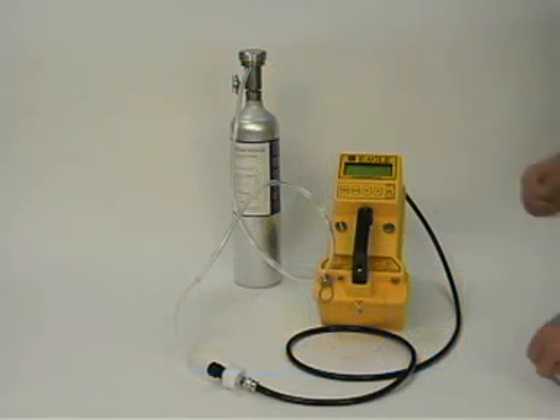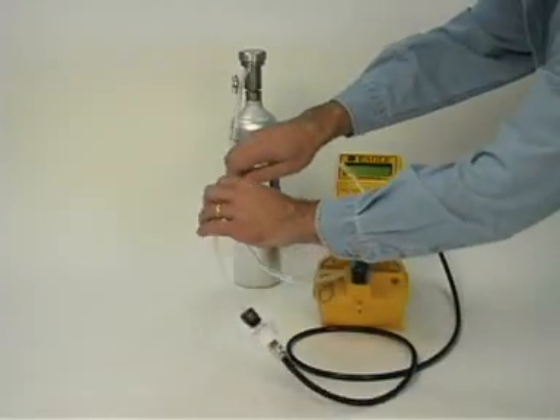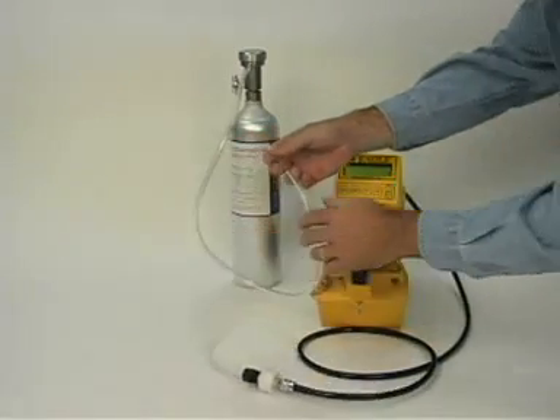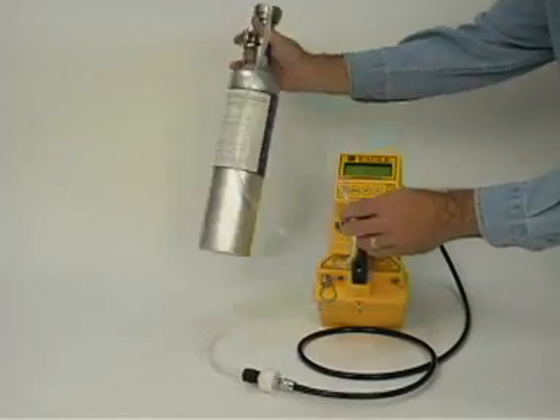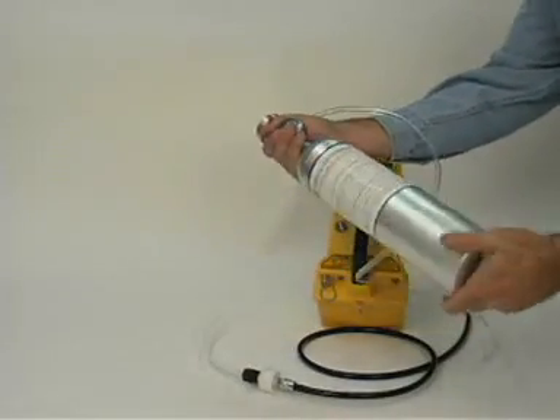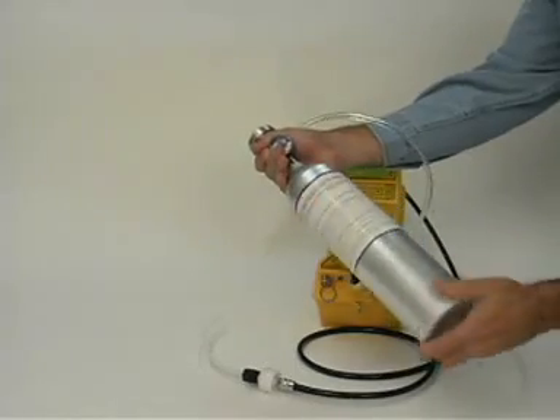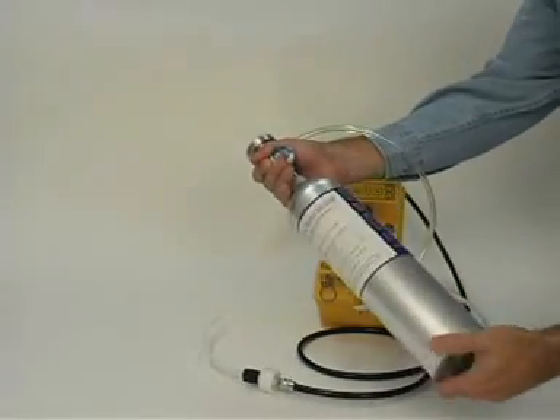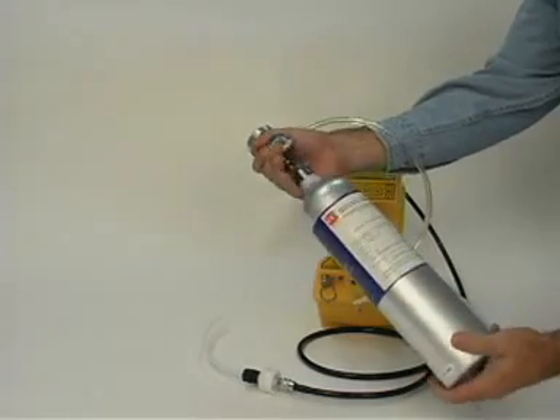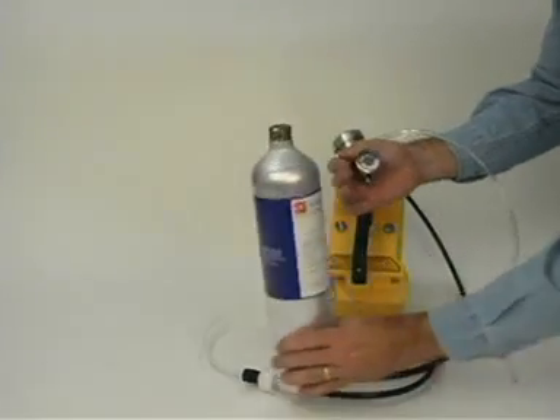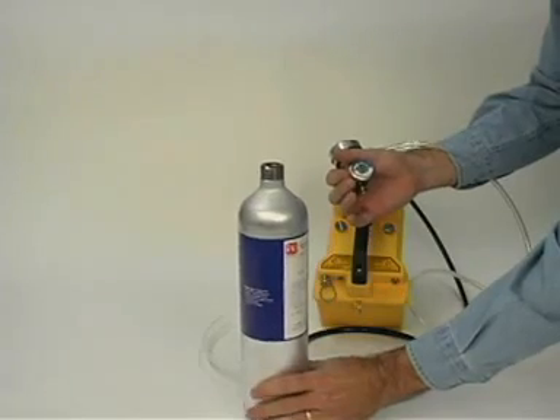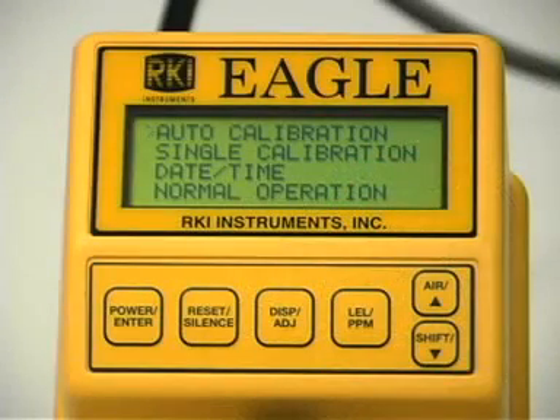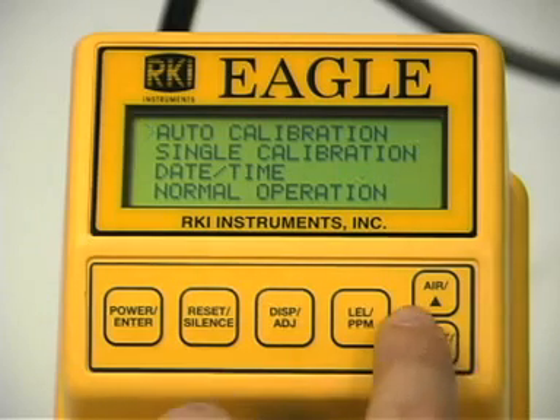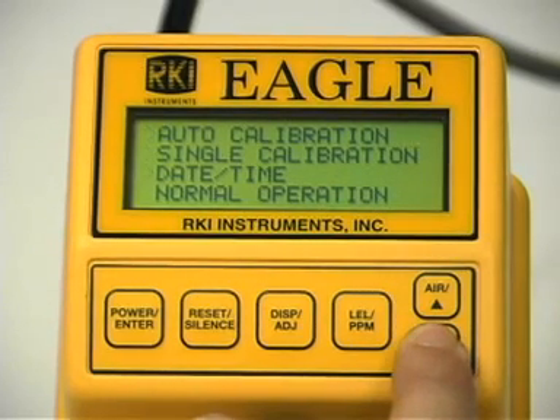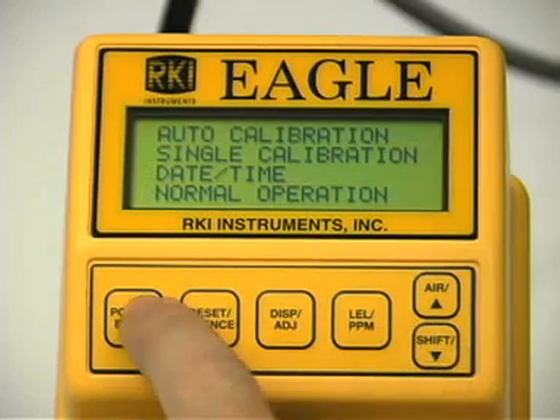Next, disconnect the tubing from the probe. Unscrew the calibration cylinder from the regulator. Press the down button to place the prompt next to the normal operation menu option. Then press the enter button to return to the normal operation screen.